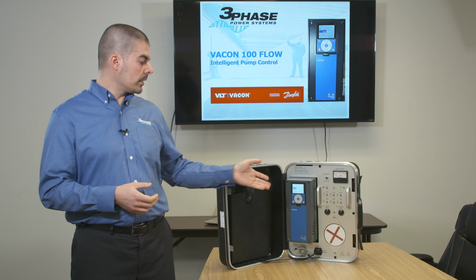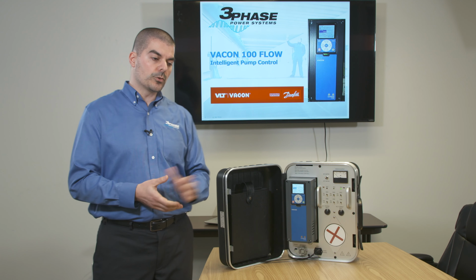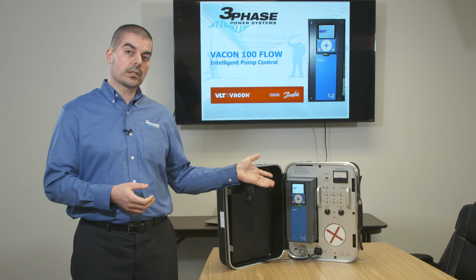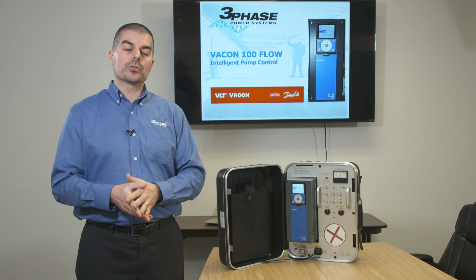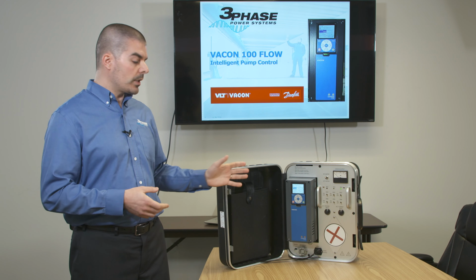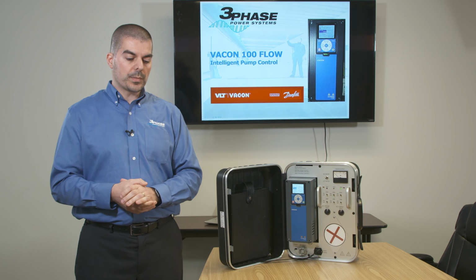In the case of the VACON 100 Flow, we have automatic protection, a setting inside the drive that can tell the drive that there is a motor disconnect switch, and it simply would slow down and speed up if this switch should be operated under load. So the drive is very unique and smart in that respect.